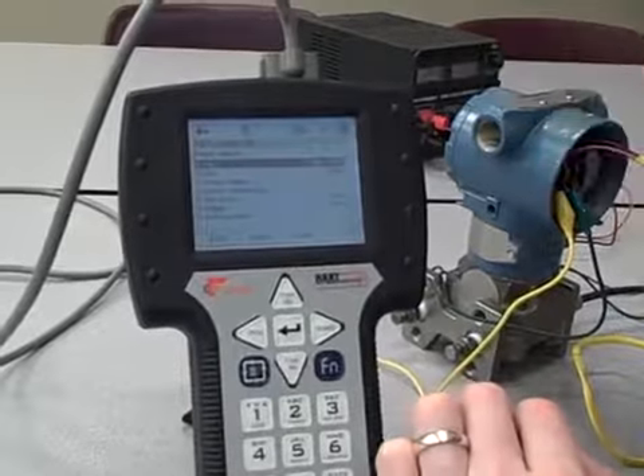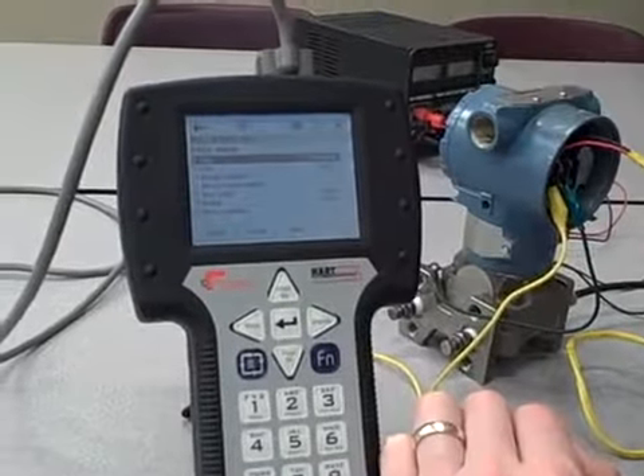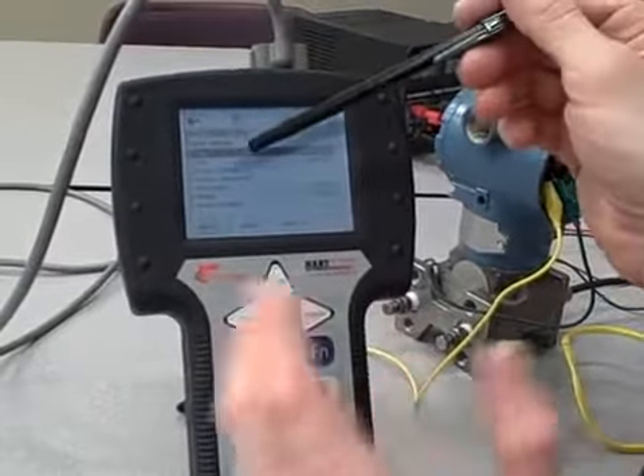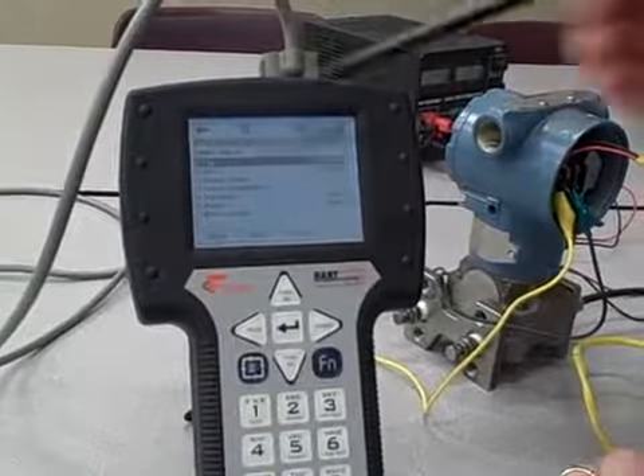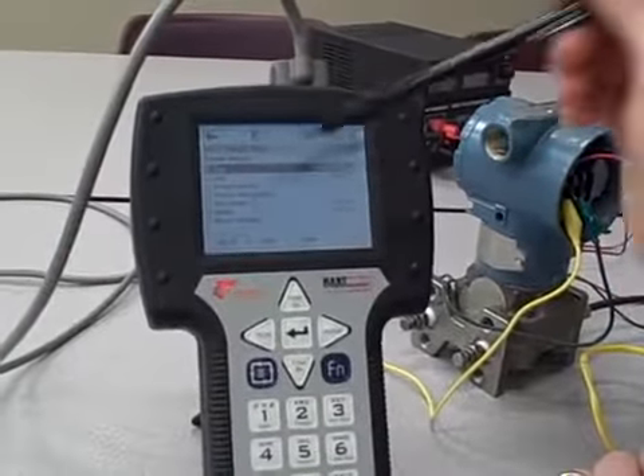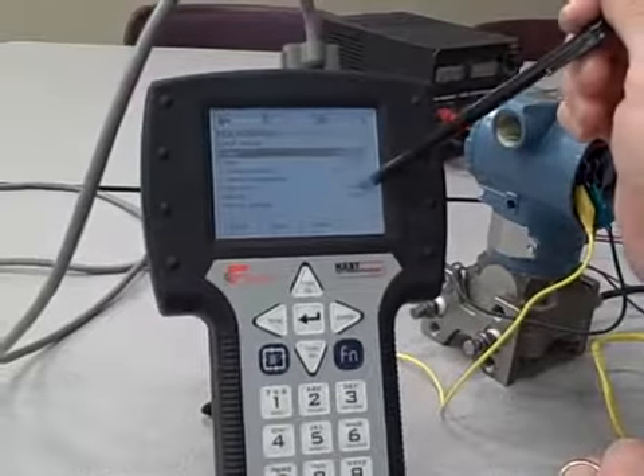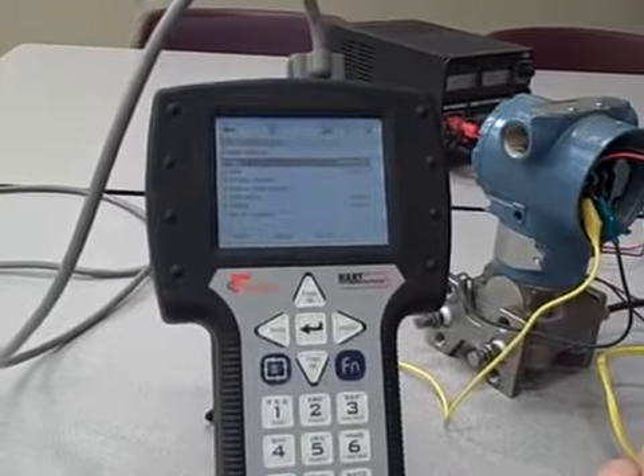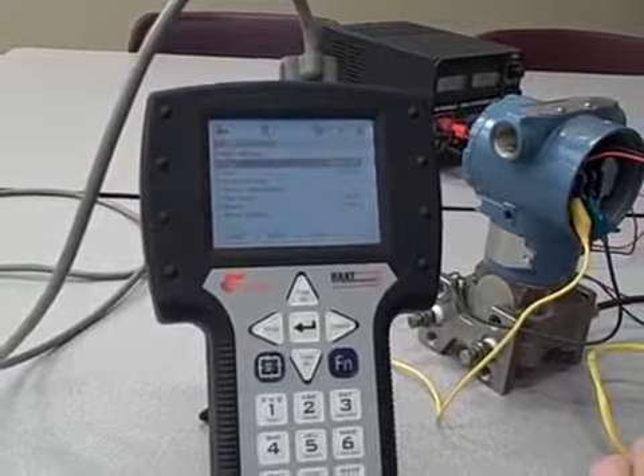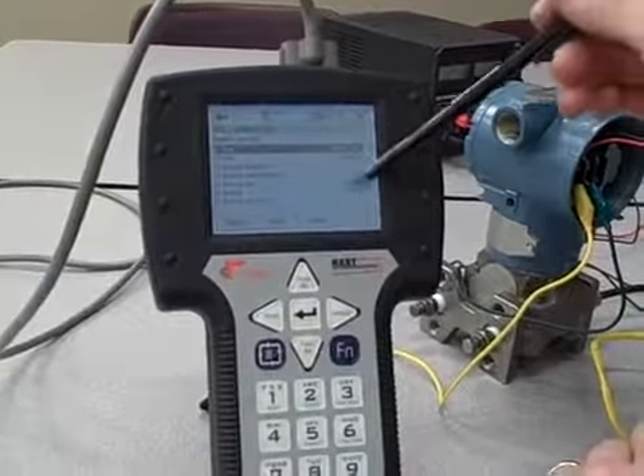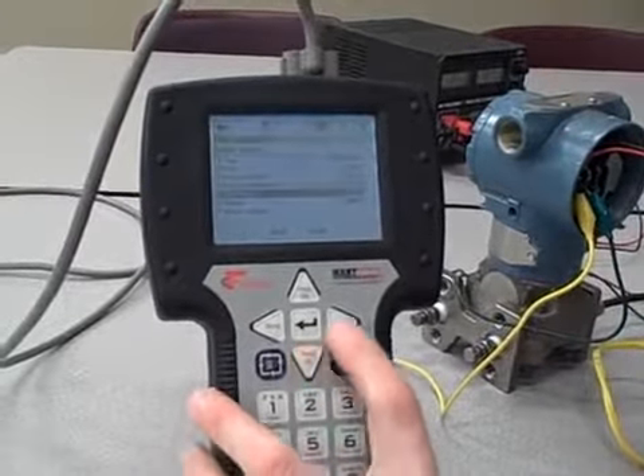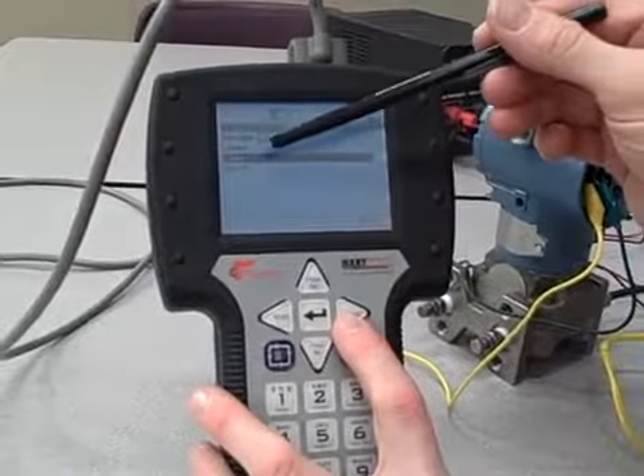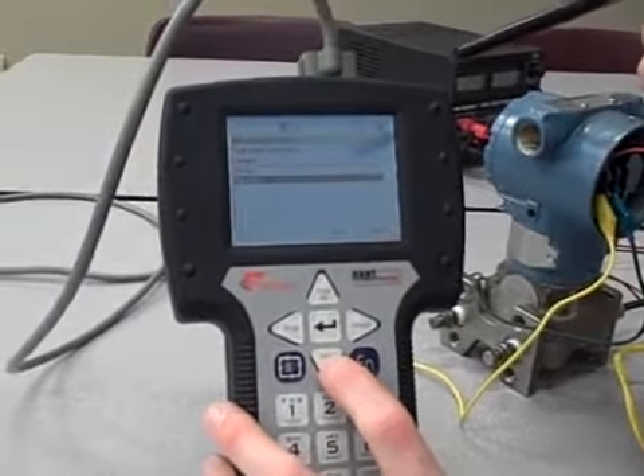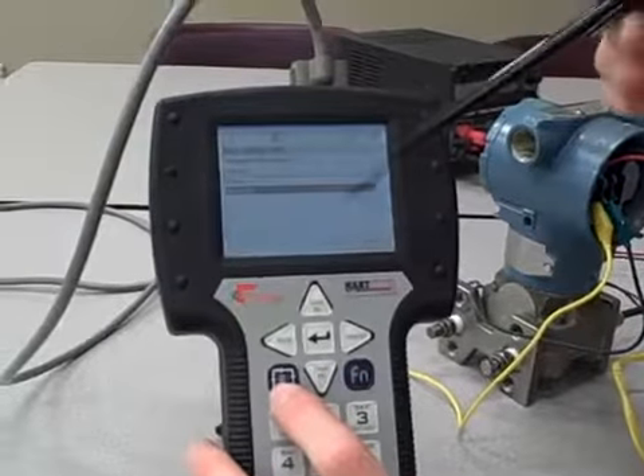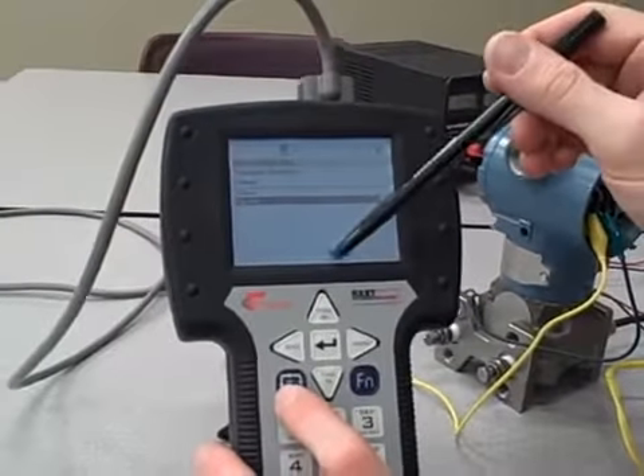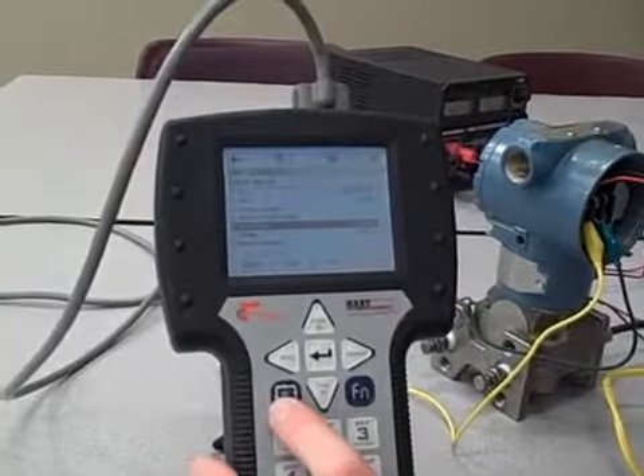I can give it a tag name, tell it what unit of pressure measurement to measure in, and the range values, once again, one more place to set the range values. I can program various device information. I can set the transfer function. In this case, it's linear. In some cases, I may want to have the transmitter apply a square root characterization function, and that's where I would apply that. For example, stepping into that menu, I can choose linear or square root. Square root, of course, is appropriate for measuring flow through a pressure-dropping element, such as an orifice plate. In this case, I want to keep it linear.